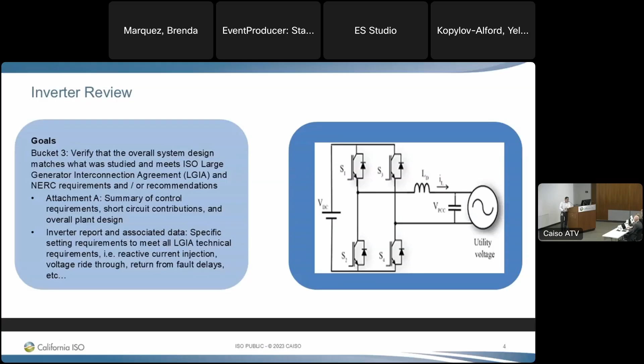Also, something that's not necessarily listed in attachment A, but is part of the LGIA, is our data requirements. You have to be synchronized to a GPS clock, with synchronization up to 1 millisecond. And then all inverters must record data on a 10 millisecond granularity, tagged to that synchronization of 1 millisecond. The triggers for data recording need to be set at 0.9 per unit and 1.1 per unit so that we can get that data in the event that you see a transient, just to make sure you're performing as required. And I think that's it.